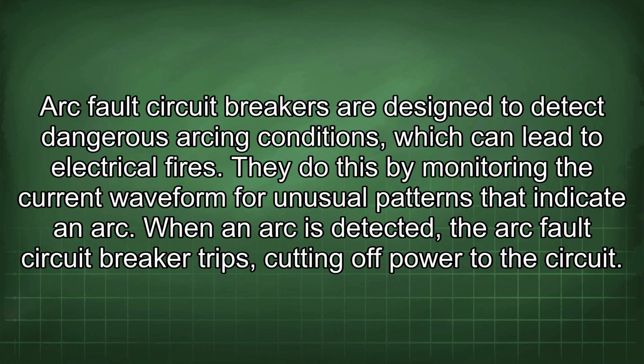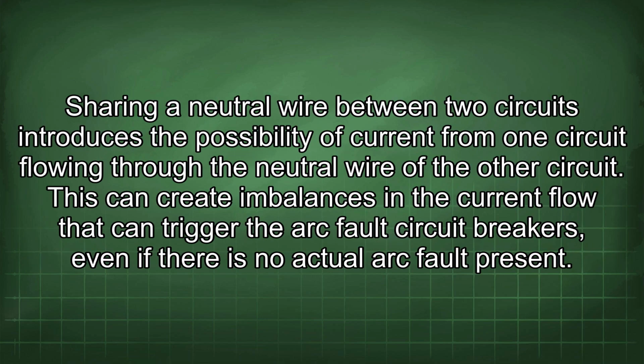Arc fault circuit breakers are designed to detect dangerous arcing conditions which can lead to electrical fires. They do this by monitoring the current waveform for unusual patterns that indicate an arc. When an arc is detected, the arc fault circuit breaker trips, cutting off power to the circuit. Sharing a neutral wire between 2 circuits introduces the possibility of current from one circuit flowing through the neutral wire of the other circuit. This can create imbalances in the current flow that can trigger the arc fault circuit breakers, even if there is no actual arc fault present.